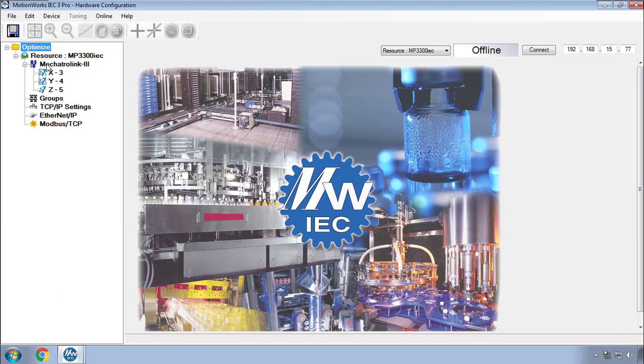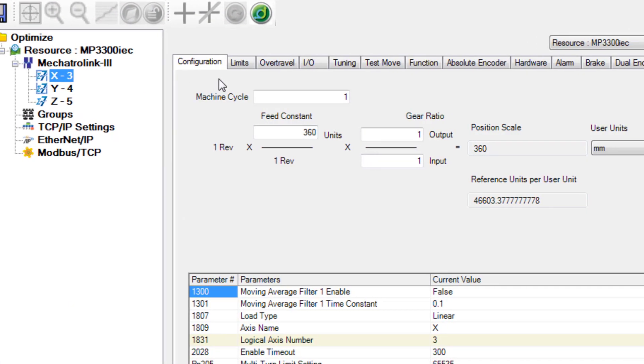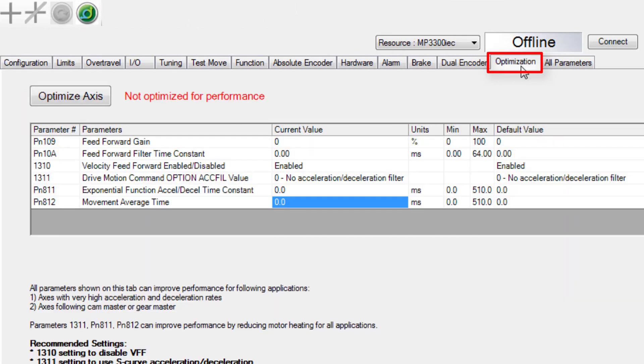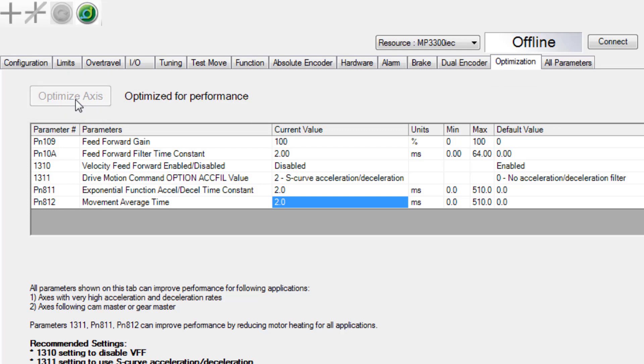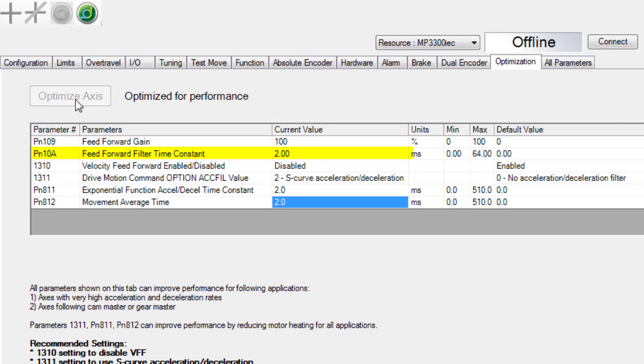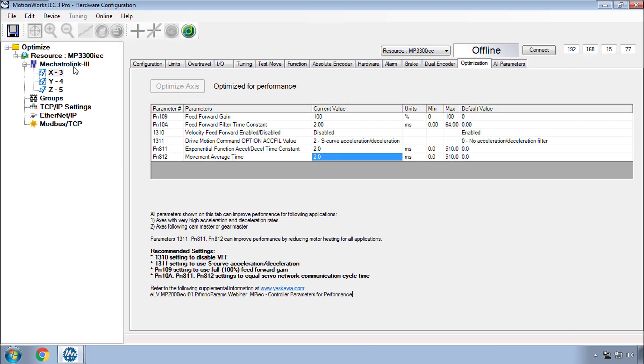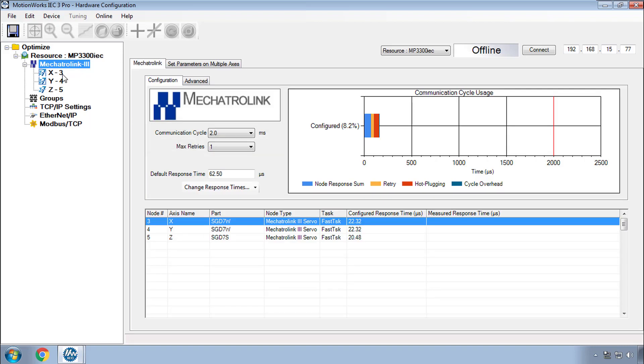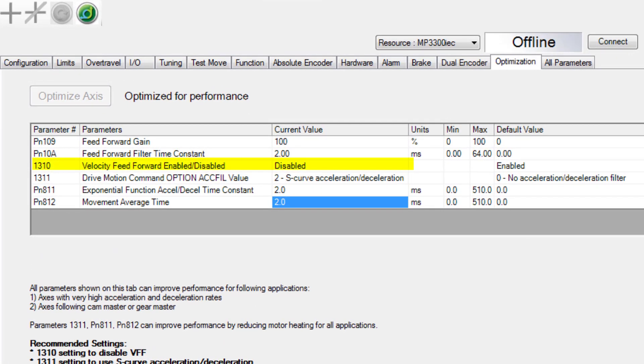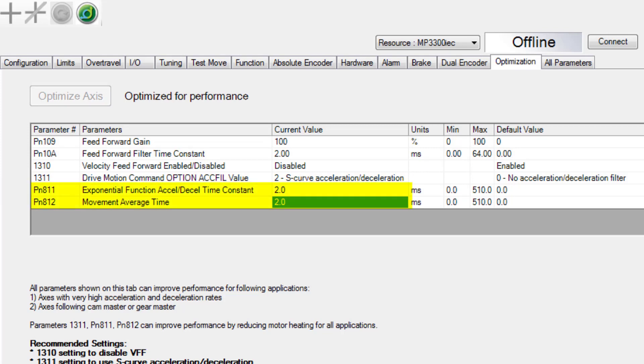If you select one of the axes in the Hardware Configuration tree, you will see the Optimization tab. When you click the button, Optimize Axis, it sets the feedforward gain to the maximum of 100%. The time constant is set to match the Mechatrolink cycle, in this case 2ms. Velocity feedforward is disabled, and an S-curve acceleration filter is applied with time constants also set to match the Mechatrolink cycle.